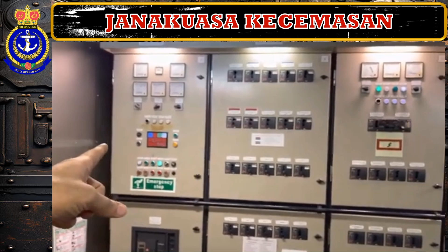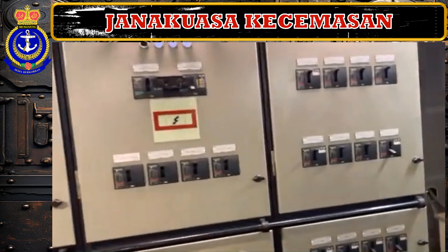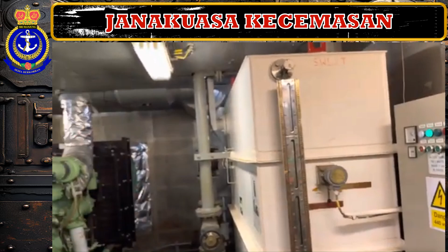this is the main feeder panel. One is the emergency generator control panel, 440 feeder panel, 220 volts feeder panel, and this is again a volt feeder panel right here. And this is the fuel oil tank for the emergency generator, which is required by SOLAS, like a minimum level at least for the fuel oil to sustain. For an oil tanker it is 18 hours fuel oil consumption at 100% load, and for our ship it is 1,200 liters, and we have marked also this is the minimum level. This is the minimum level. A float type switch will give us an alarm in case the level drops down.